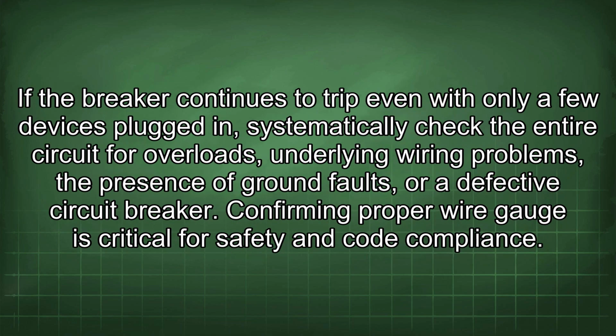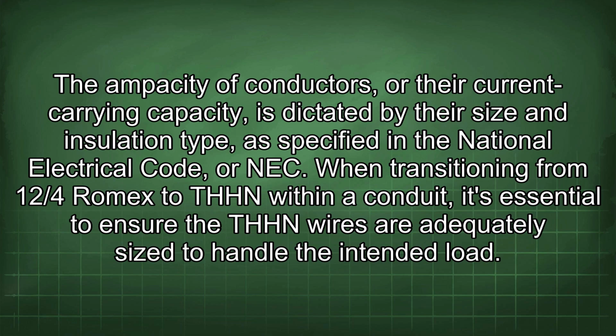If the breaker continues to trip even with only a few devices plugged in, systematically check the entire circuit for overloads, underlying wiring problems, the presence of ground faults, or a defective circuit breaker. Confirming proper wire gauge is critical for safety and code compliance. The ampacity of conductors, or the current carrying capacity, is dictated by their size and insulation type, as specified in the National Electrical Code, or NEC.